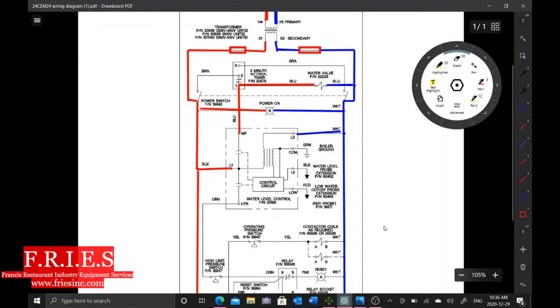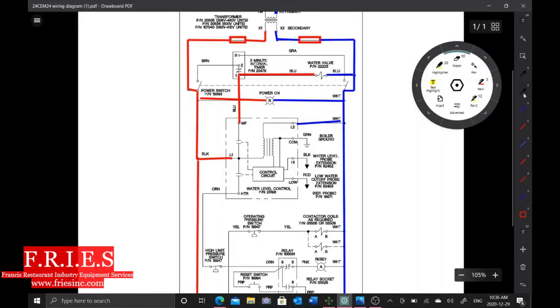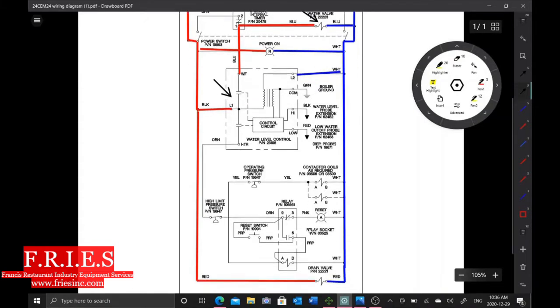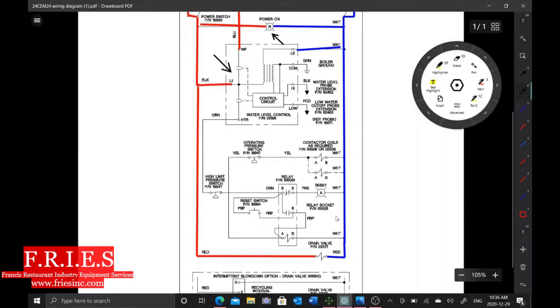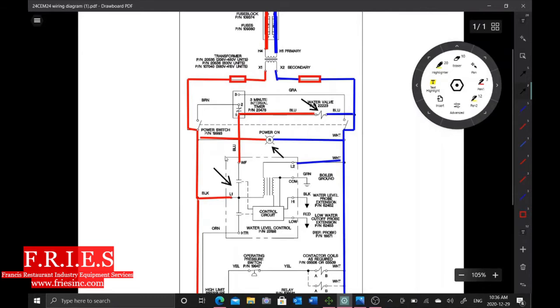All right, so the next thing I did was isolate all four of those components that I feel like could be the issue. Sorry, you can't see it in the video—I was videotaping someone else, I didn't really want to show them in the footage. That's also why there's no audio in any of it. So what I did was remove the four loads: I disconnected the wiring here, I disconnected the wiring to this board, I disconnected the wiring to this light, and I disconnected the wire to this drain valve. Now as soon as I disconnect the wiring to this board here, this water valve is kind of out of the circuit, so these two have to be connected together.